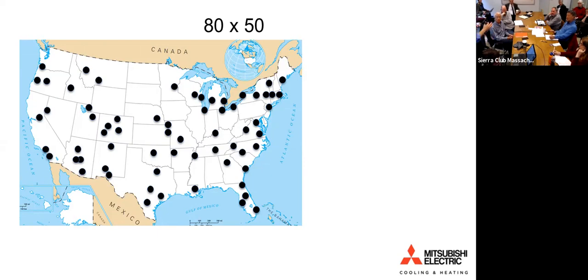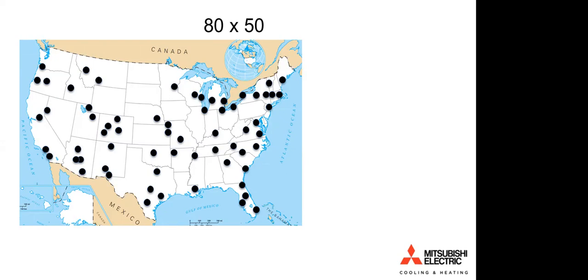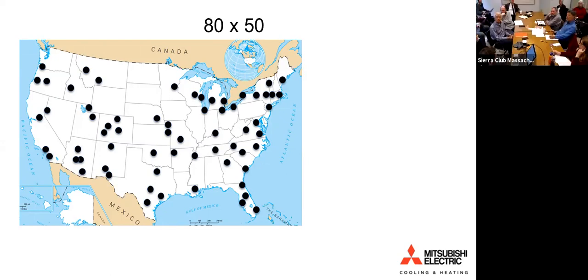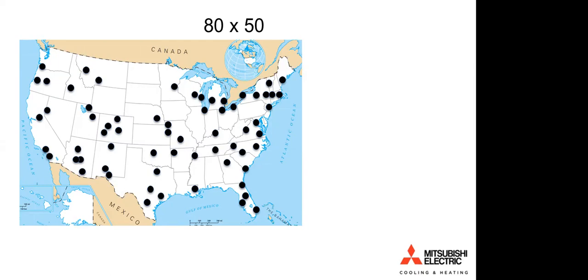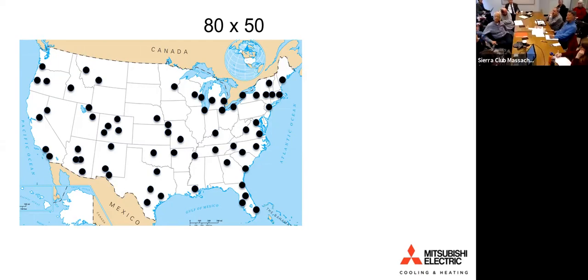On the other hand, there are also air-to-water systems that aren't as prevalent here in the United States. They're common on the commercial side, but not quite as prevalent on the residential side, and there's a whole host of reasons. One big reason is that our water systems, our boilers, run at high temperature, while air-to-water heat pumps provide low temperature, so you can't put it through the same baseboard. But on a new construction home, it's terrific, with radiant heat in the floor, very efficient systems.